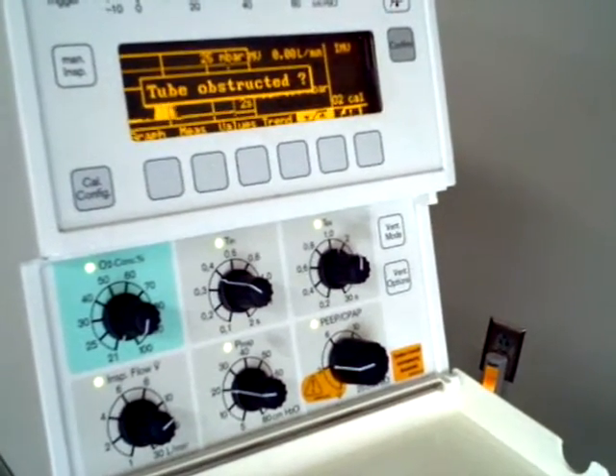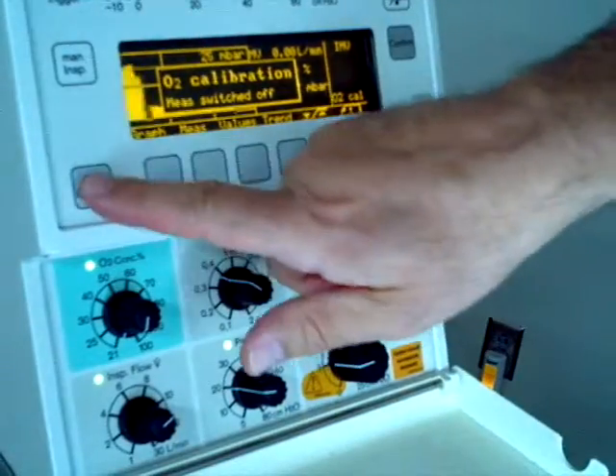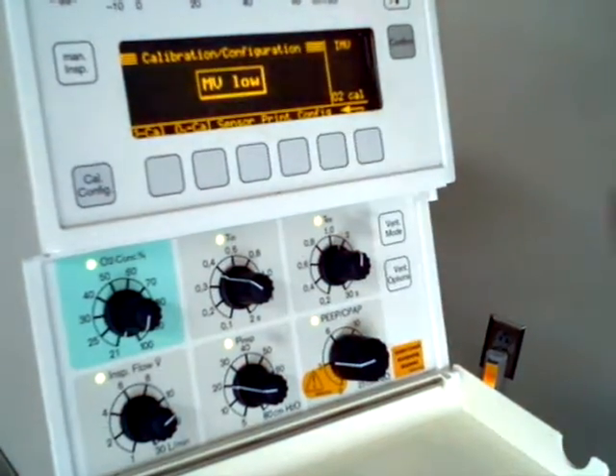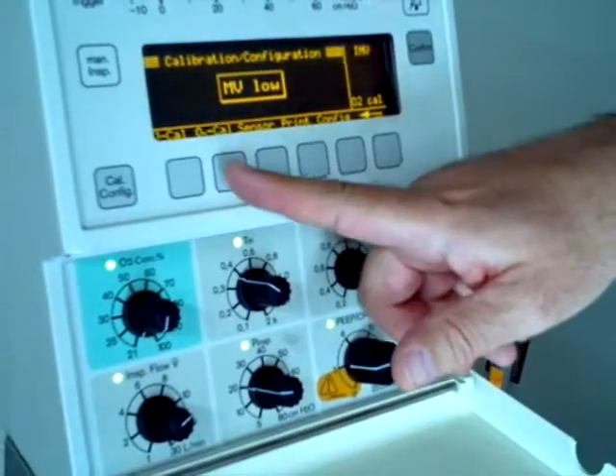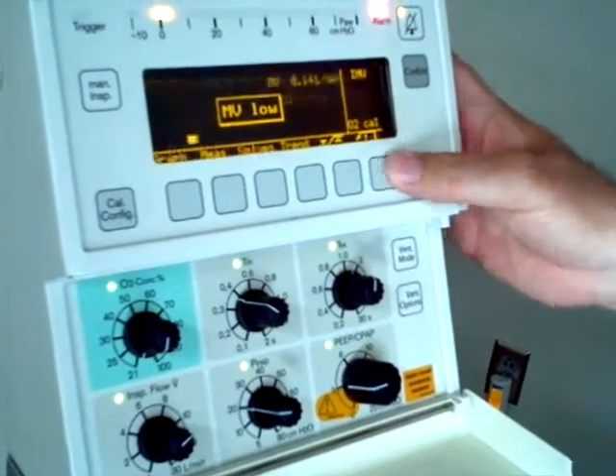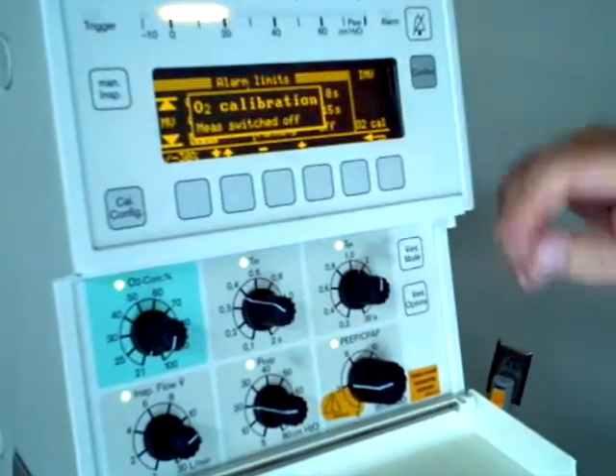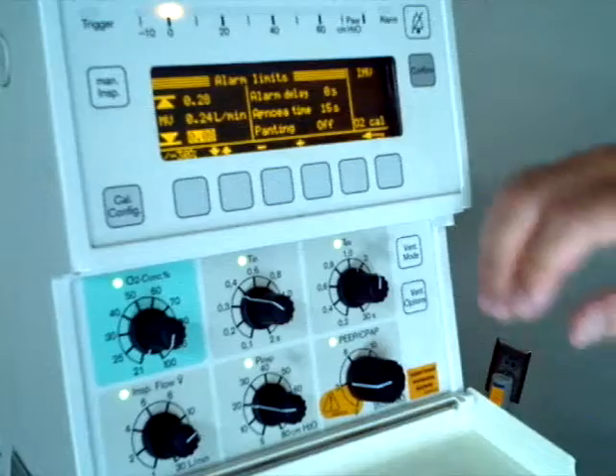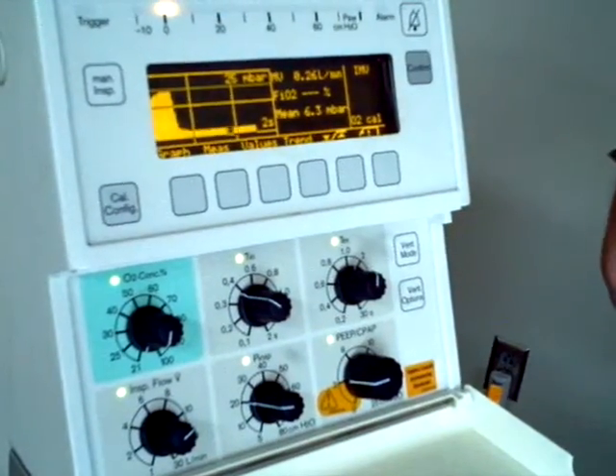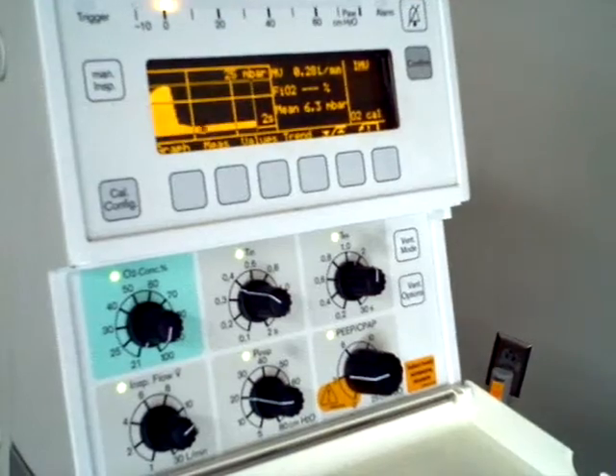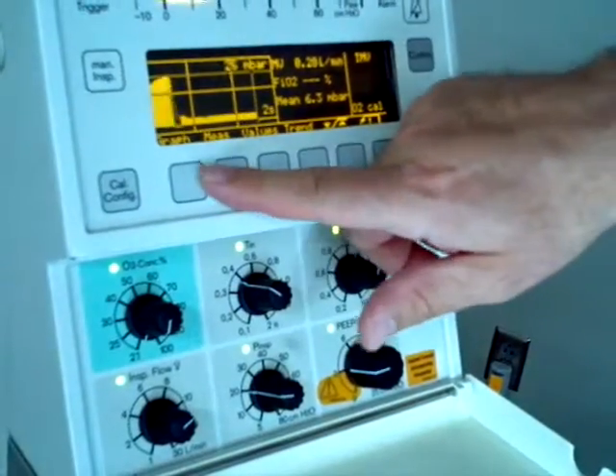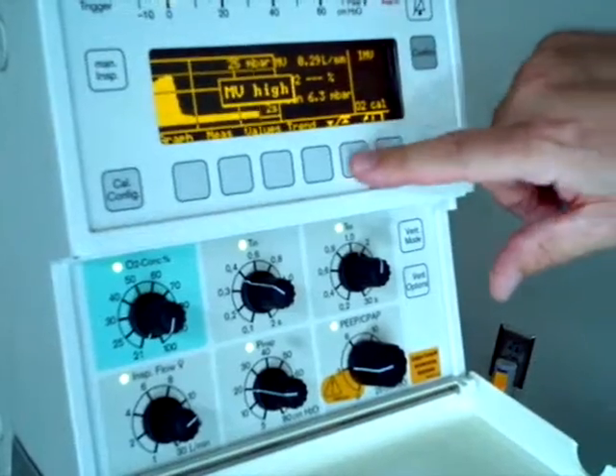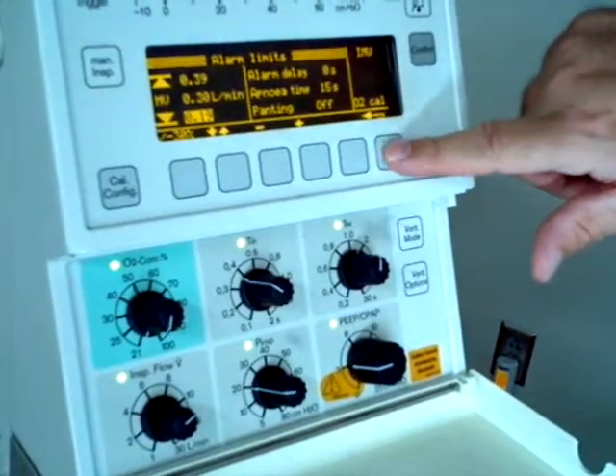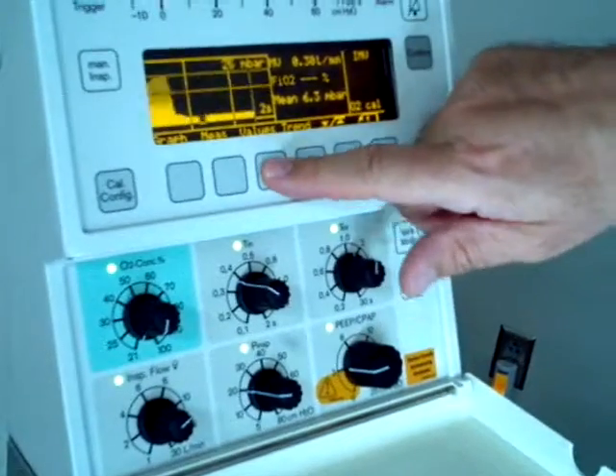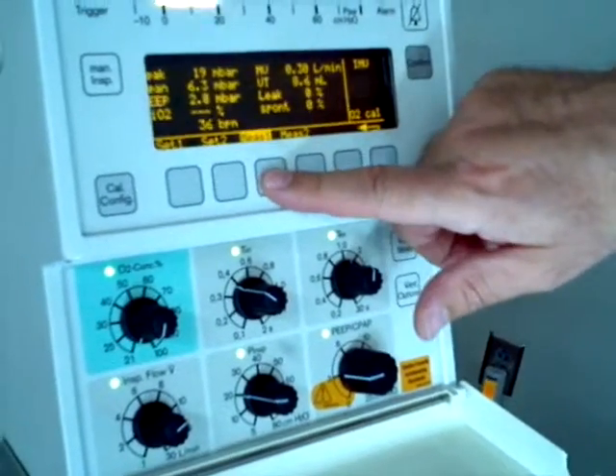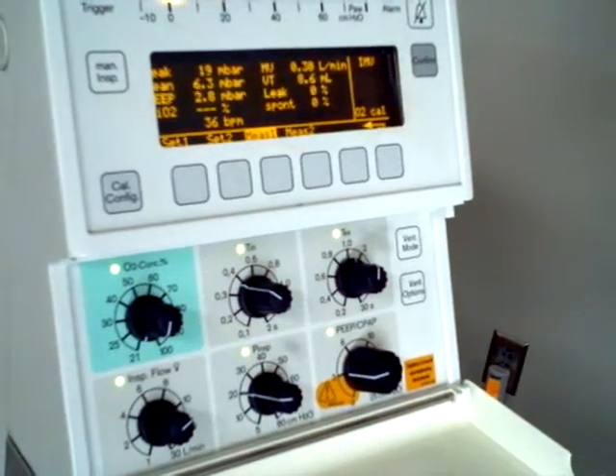Okay. And then what I'll probably have you do is go back to your cal config. There's O2 cal. So if you just change out a new O2 cell, you need to calibrate it. It's the same process. You just press that there. I'm going to quickly reset our alarms. Okay. Verify tight system. There's different ways you can do that. You could look at your leak percentage on your measured screen.